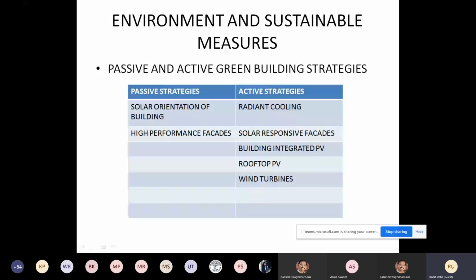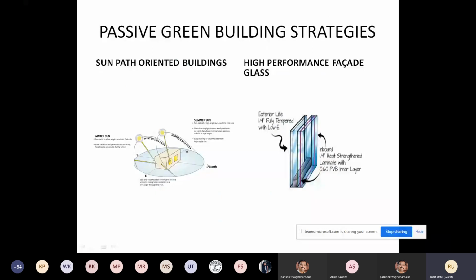If you look at the passive green building strategies, as I said, you can actually orient the building in a manner where the glass and the openings are more towards the north side, so more light is let in, yet the heat is kept out. As you can see, the winter sun moves in a different trajectory, and the summer sun also moves in a different trajectory. And on the right hand side, you can see the various types of high performance glass, where there's laminated glass, and then there's an air gap filled with some kind of neutral gas like argon, and then you have the third glass, which is the external side of the glass. So all these things contribute to reducing the ingress of heat, and because the heat ingress reduces, your air conditioning needs are much lower, and the energy which is used up in the air conditioning system starts to go down.